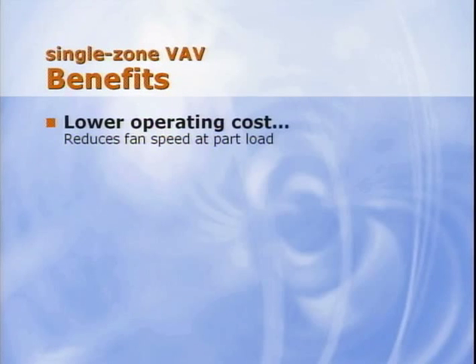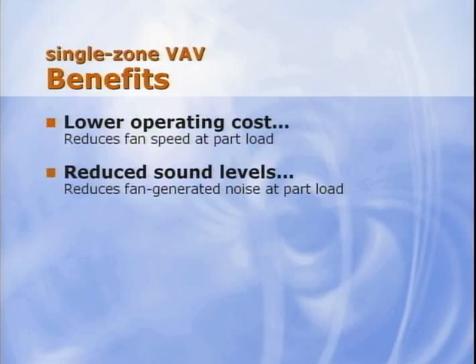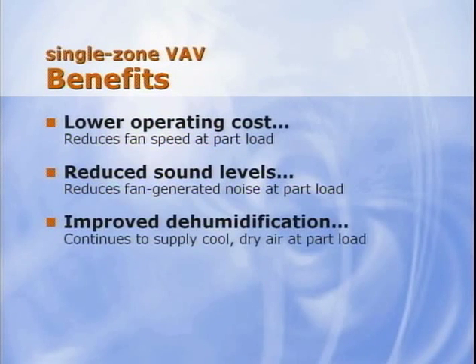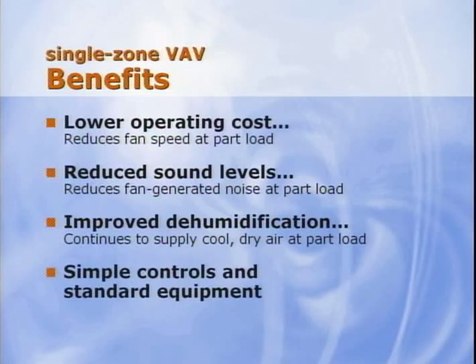Single-zone VAV is an excellent system for large, densely occupied zones that have variable cooling loads. Common examples include gymnasiums, lecture halls, arenas, auditoriums, and places of worship. Compared to a constant volume system that is often used for large zones such as these, a single-zone VAV system results in fan energy savings and less fan-generated noise at part load conditions. It also improves part load dehumidification because the system continues to deliver cool, dry air at part load conditions, which could save energy in the reheat region. Finally, the controls are relatively simple since there are no VAV terminal units to coordinate. Standard equipment can typically be used.